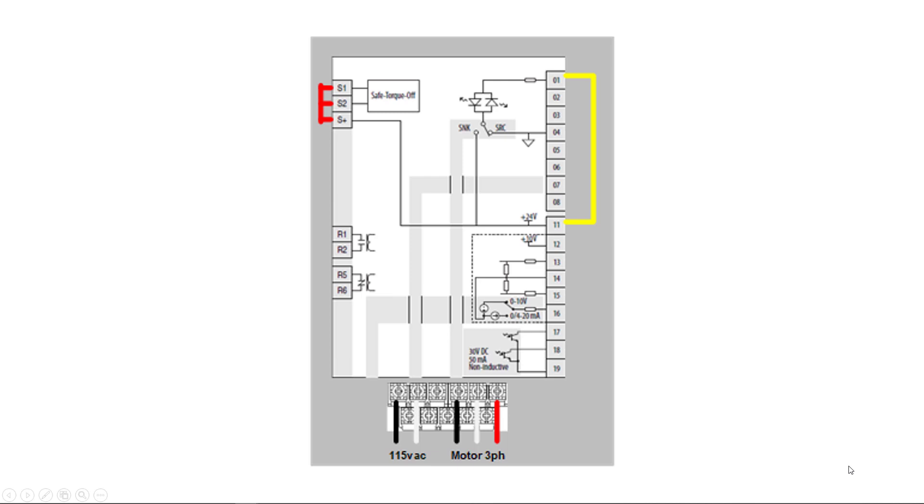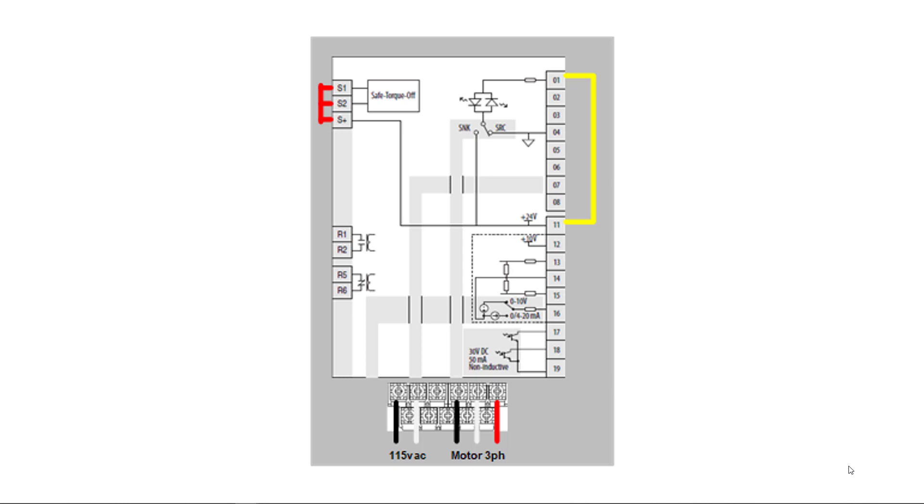What I'm striving to do here is for those of you that don't have a variable frequency drive to play with, is to give you as close to a hands-on experience as I can manage with this camera and the equipment that I have. First let's look at this drive schematic view or diagram view. The yellow conductor is going from terminal 1 to terminal 11. These terminals are in two rows right next to each other so the distance from 1 to 11 is very short.